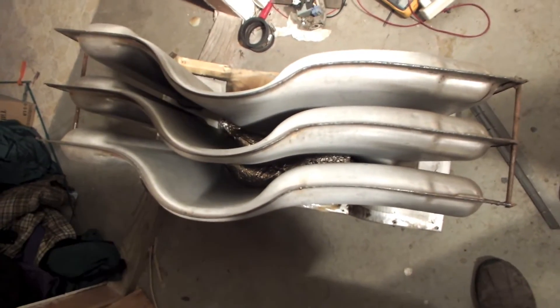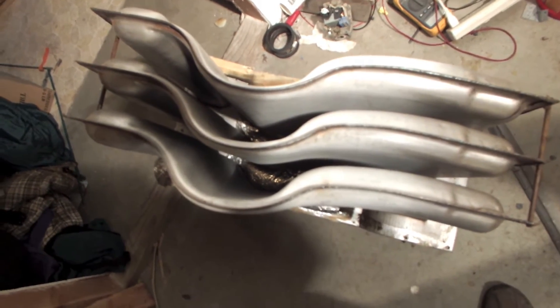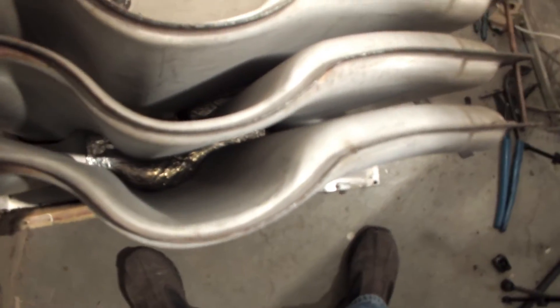This is a Lennox curve heat exchanger — it's called the curve because it curves. A lot of these things broke, and where they would usually break is right in there where I'm getting close up on, where this thing snakes down and starts going up. Right in there — very common for them to break.